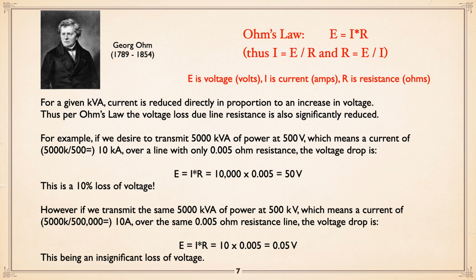Now, if we transmit the same amount of power, 5,000 kVA, at 500 kilovolt, which is 500,000 volt, that means a current flow of 10 amp over the same 0.005 ohm resistance. The voltage drop is only 0.05 of a volt. Well, obviously, if we came into this thing at 500,000 volt and lost 0.05 of a volt, it's insignificant. That's why they can do these super, super long lines without losing that much power, because the voltage is so high.